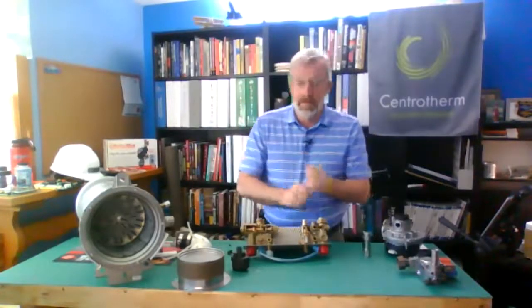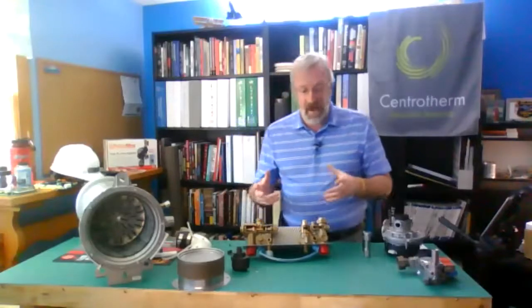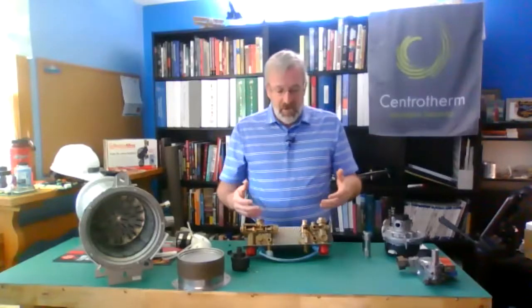Now, to tell you if you actually have a domestic call, two things will happen. One is the red light that's here on the flow sensor will light up. The second thing is you will get an indicator on the display showing it's a steady faucet, spigot looking thing. If it's a flashing spigot, faucet looking thing, the boiler's in what we call domestic hot water preheat. And what it's doing then is it's actually keeping this warm. And when the boiler's off, or there's no call for domestic hot water, it's sitting there all day long.